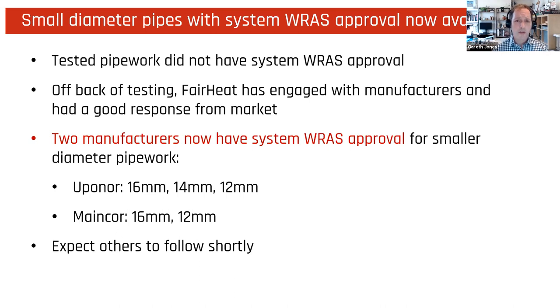One other thing we want to note is that when we went through the testing originally, the pipework that we tested didn't actually have system WRAS approval, which you need to have. We then engaged with manufacturers off the back of that test and got a really good response from the market. We've got two manufacturers who now have system WRAS approval for smaller diameter pipework.